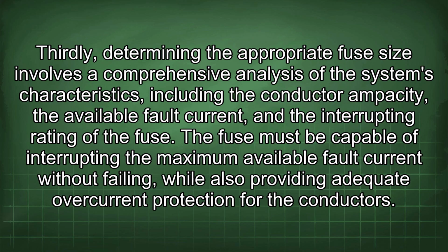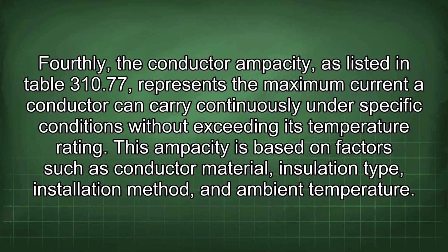Thirdly, determining the appropriate fuse size involves a comprehensive analysis of the system's characteristics, including the conductor ampacity, the available fault current, and the interrupting rating of the fuse. The fuse must be capable of interrupting the maximum available fault current without failing, while also providing adequate overcurrent protection for the conductors.